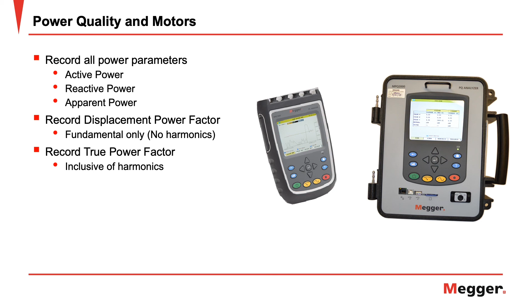It will record both transients and subcycle distortions that can cause bearing pitting and fluting, as well as insulation breakdown, which will lead to shorted coils. The analyzer will also record all power parameters, as well as power factor. A low power factor can cause motors to be unable to obtain full power.